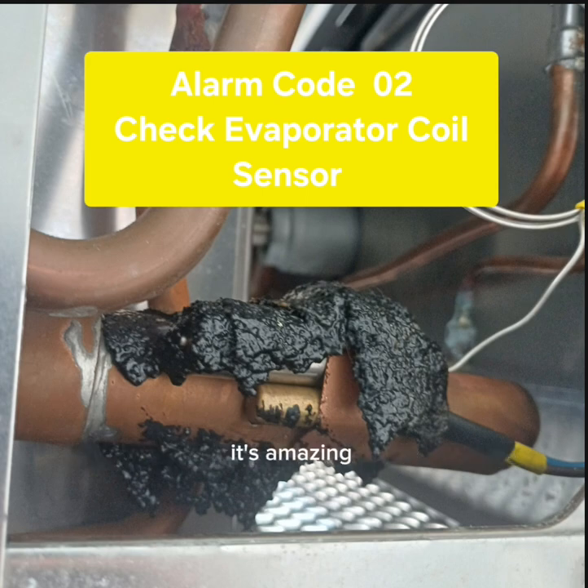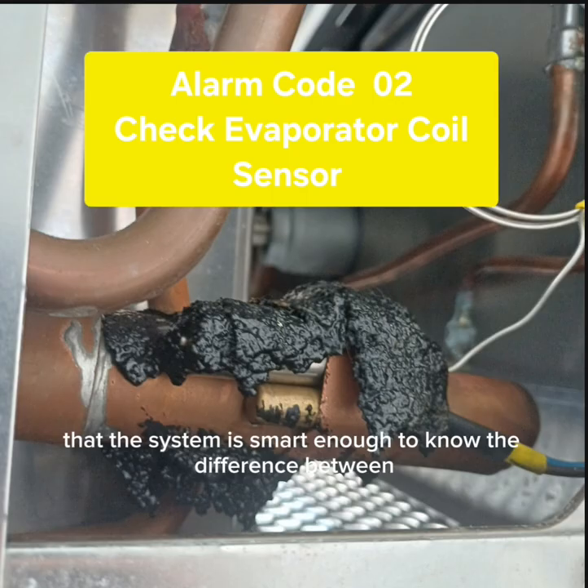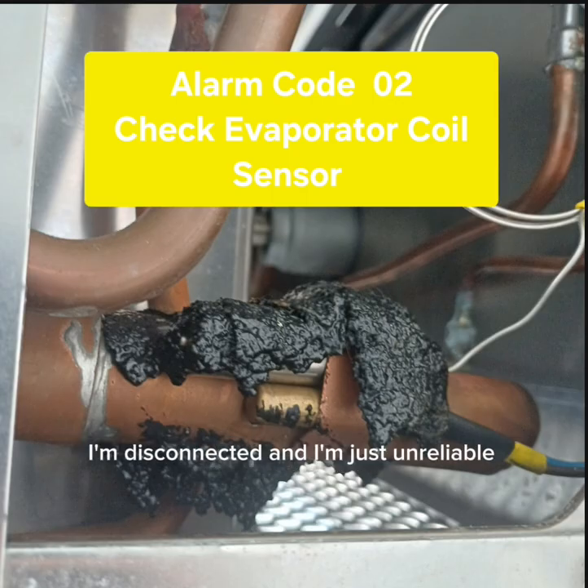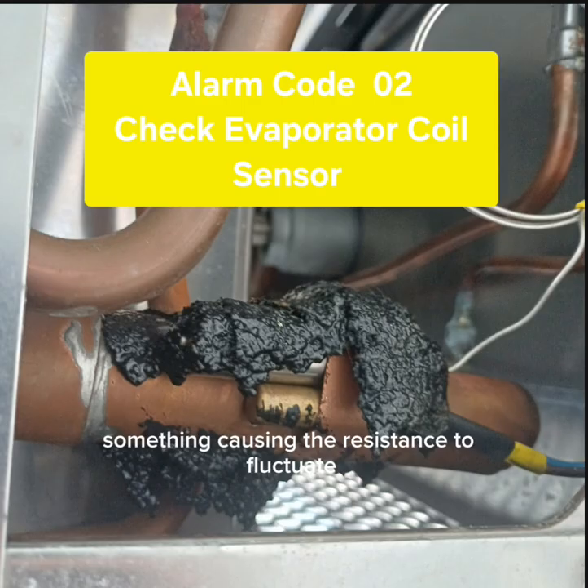It's amazing that the system is smart enough to know the difference between I'm disconnected and I'm just unreliable. It's vital for diagnostics. Yeah. A hard failure, dashes, I'm looking for a cut wire or a loose pin at J3. A soft failure with alarm 13, I'm thinking moisture intrusion, something causing the resistance to fluctuate.